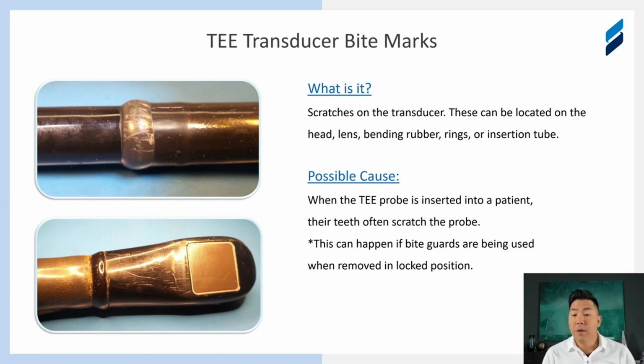This slide is about bite marks and scratches, specifically on a TEE. When this goes down the esophagus, you can see in the pictures here that there are a lot of scrapes and scuffs. It can become an issue if those are severe enough to expose the internal electronics to the patient, to soaking fluids used to decontaminate these probes, causing shorts internally because the fluid will get into the transducer.